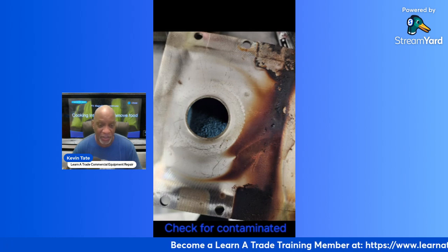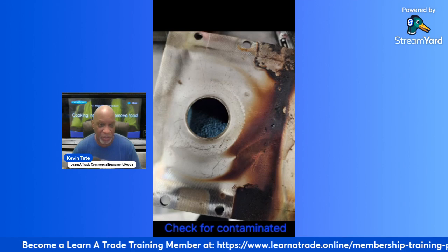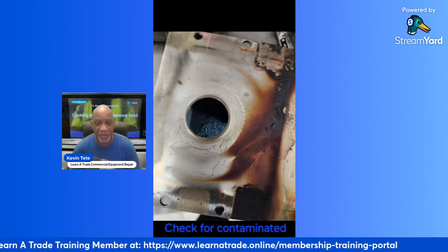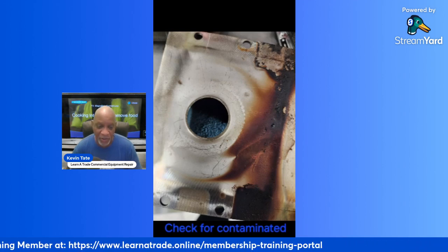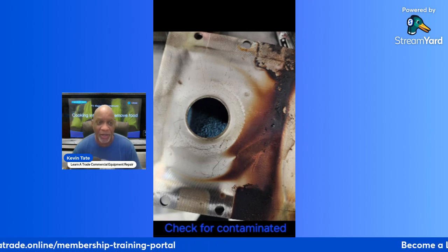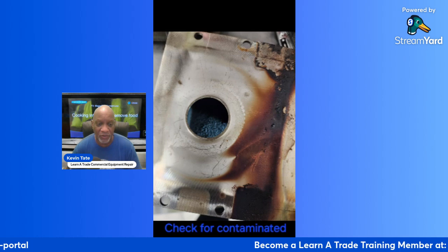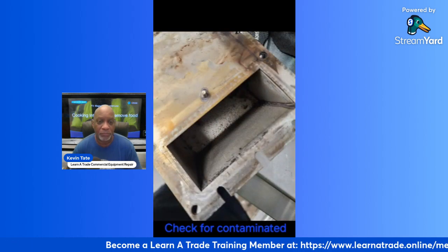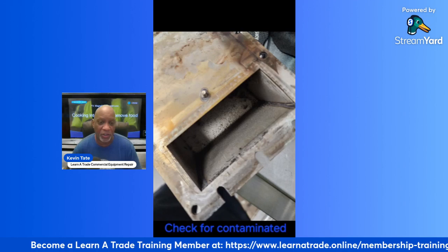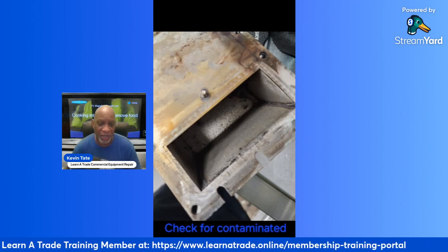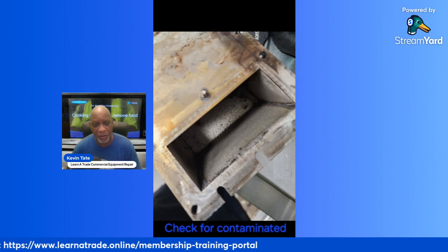If you're able to clean it and put it back in and get the machine back up and running, then that's fine. But if you still have contamination in that waveguide, it's better that you just leave the machine down and then return when you can replace both waveguides. This is just the bottom portion of that waveguide. You can see there's still contamination in there.